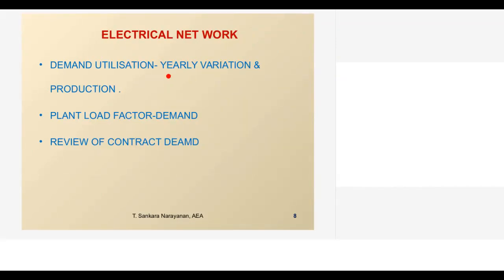So we normally take under the audit at least 2 years of data, to see how the yearly variation in production and demand varies. Then also plant load factor and demand, because some of the states give load factor incentive. Then in certain cases, we need to review the contract demand for two reasons. Whether I am underutilizing the contract, because there are minimum billing clauses, or sometimes there may be an increase in contract demand, because normally for an industry, if there is an increase in contract demand, immediately there will be a penalty.